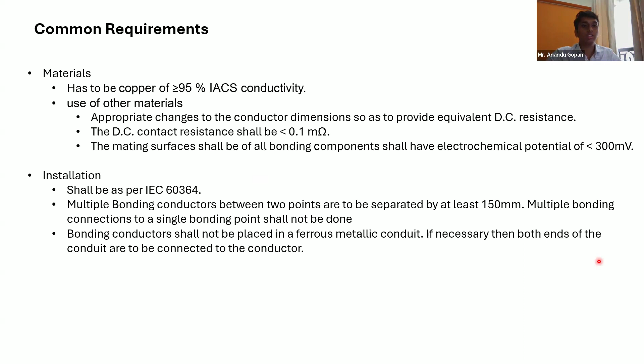And multiple bonding to a single bonding point is also not allowed, because during maintenance you can remove this, and your entire electrical system will be in jeopardy. So it should not be to a single bonding point. You can have multiple bonding points with 150 mm separation distance. And these bonding conductors should not be placed in a metallic conduit. If it is going to be placed in a metallic conduit, you have to bond the ends of the metallic conduit to the bonding points.